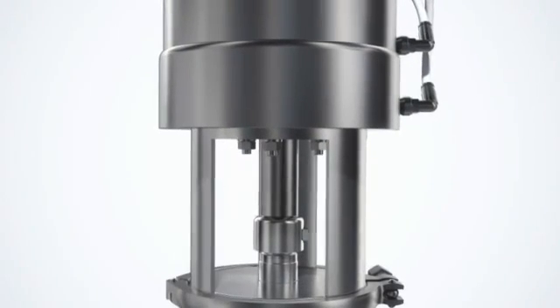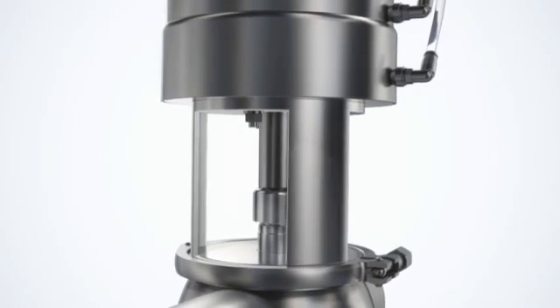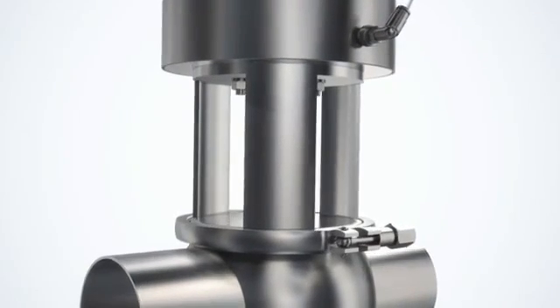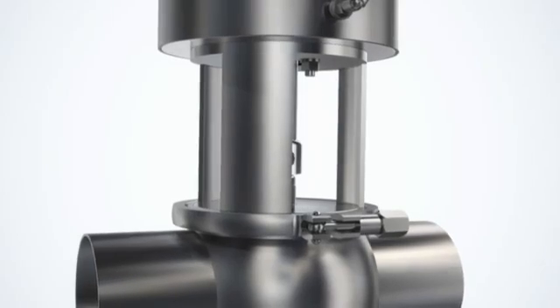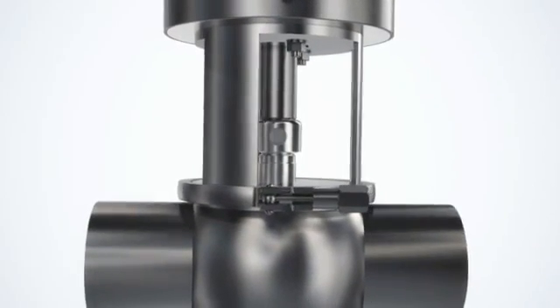For easy dismantling and fast maintenance, the valve body features a top loaded design and clamps for easy disassembly and reassembly. Built-in leak detection, defined compression of static seals and double acting lip seal technology eliminate the risk of product contamination.